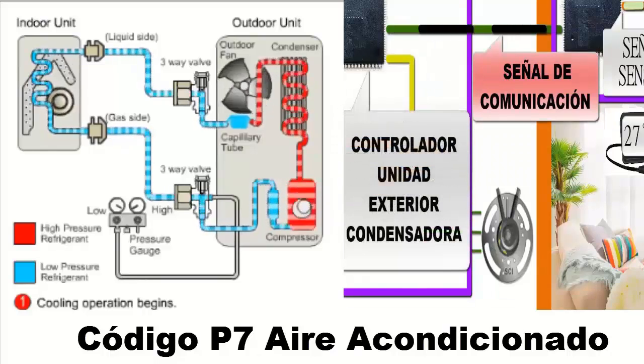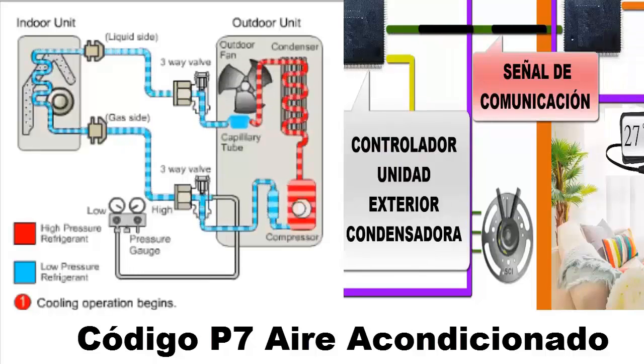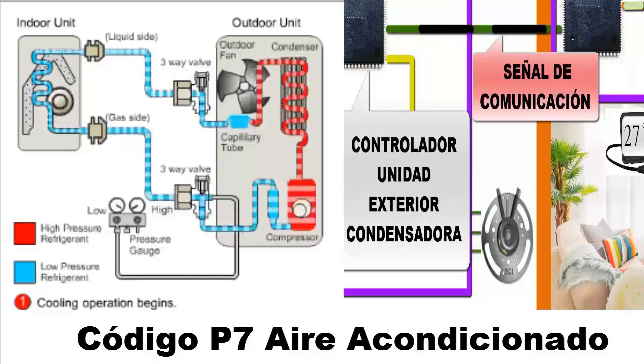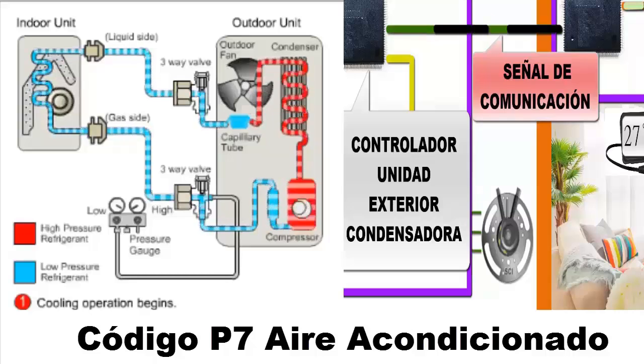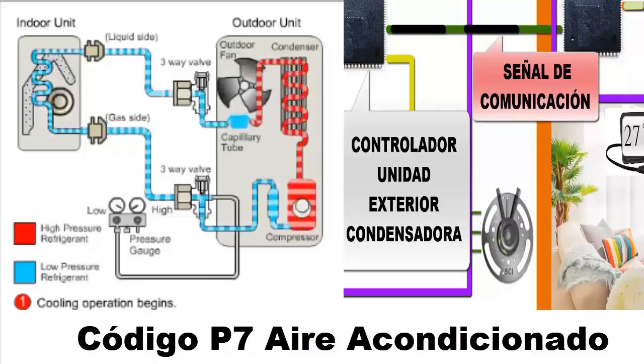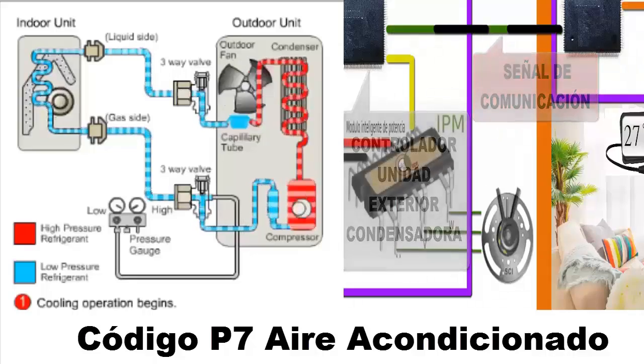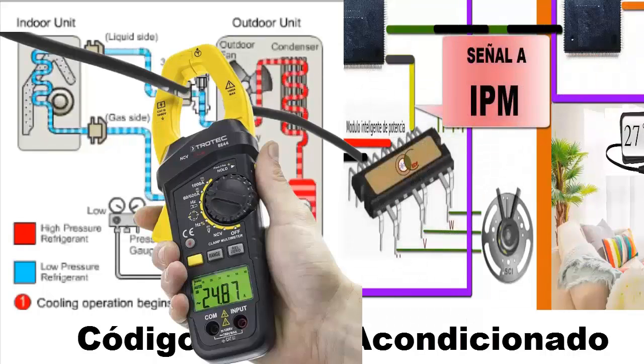In addition to firm contact between the aluminum heat sink and IPM, it is essential to check that the heat sink fins are free from any dirt, such as dust or other substances that limit heat transfer. If the code persists after checking these points, it will be necessary to measure the current consumed by the compressor. If the current is out of range, it may be attributed to IPM overheating.